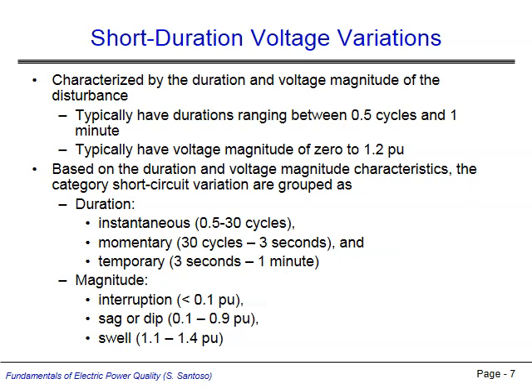If the voltage magnitude falls below 0.1 per unit, the event is called an interruption. If the magnitude falls to between 0.1 and 0.9 per unit, it is a voltage sag, or dip. If the voltage magnitude rises to 1.1 per unit or higher, the event is called a voltage swell. Voltage magnitudes between 0.9 and 1.1 per unit are considered to be within the normal operating range of the power system and are not considered a variation.